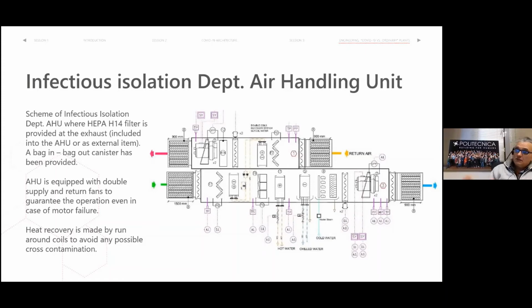This unit is provided with a HEPA H14 filter at the exhaust. Because of course, the return air coming from the infectious patient rooms can carry with it some viruses, which are generally connected to a particle. So we get the particle and we get the virus. So we clean it thoroughly there before exhausting it outside.